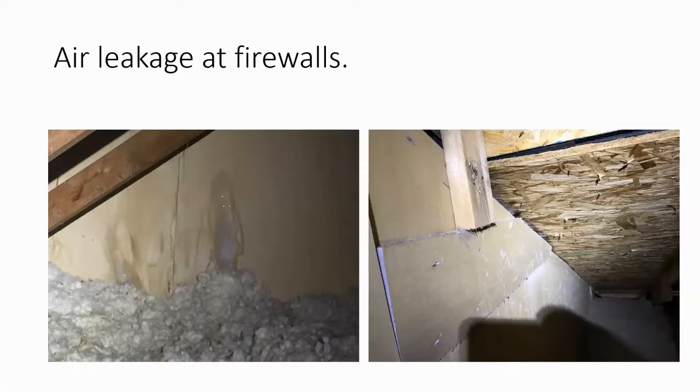And it'll leak out between the wall plate next to the firewall, and it'll leak out at the top here. I'm starting to see some very thorough specs being done up by engineering firms. The latest one was a building less than 10 years old. For sure, they were having moisture problems. The spec was to seal, and how they had spec fixing this problem was actually to cut into the firewall and spray foam down basically at the ceiling level to stop that air flow at that point.